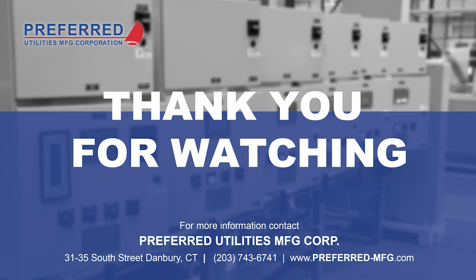So most burners will have a particular area that is more critical, and that's where you're able to really customize that. So most burner applications that I've been involved in, you'll see anywhere from 12 to about 20 points. And each one of those points, of course, is saving the position of each of the servos in the system for that point, and also like a variable speed drive 4 to 20 out, it'll save that value too. Also, if we have O2 trim, it'll be saving that particular O2 value. So about 12 to 20 points most of the time.